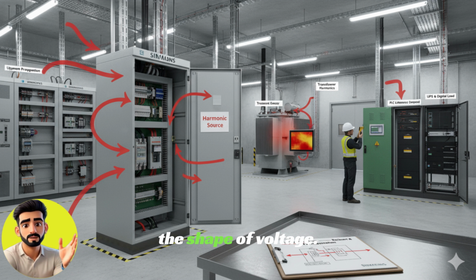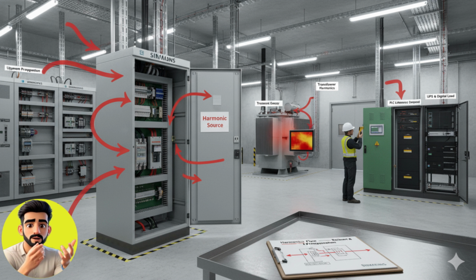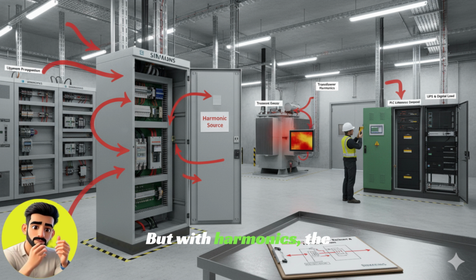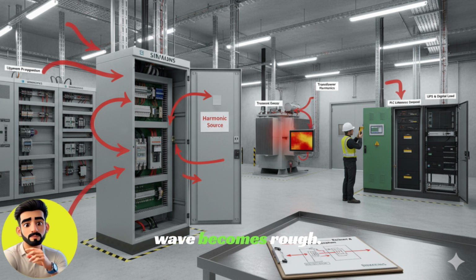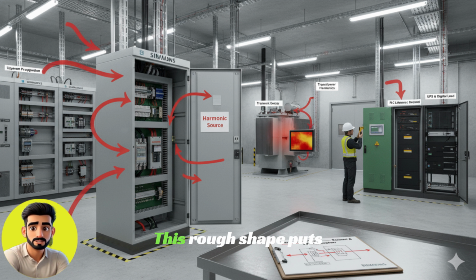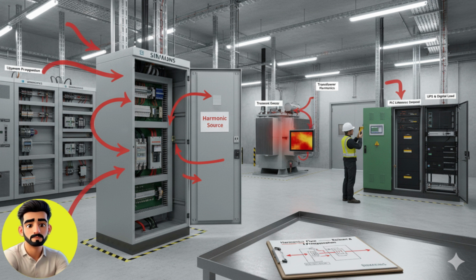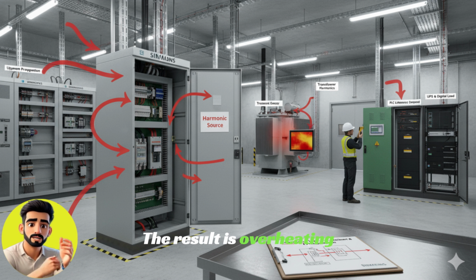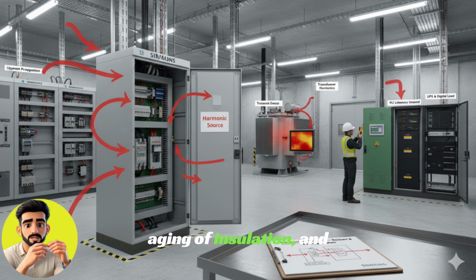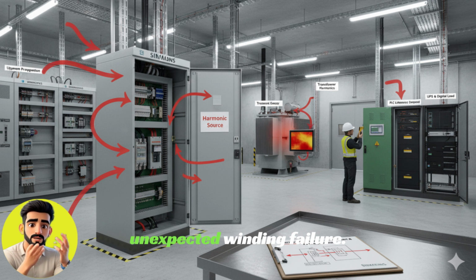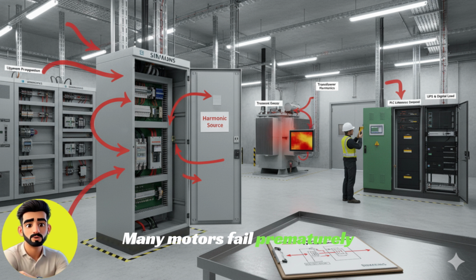Third point. Harmonics distort the shape of voltage. Under normal conditions, the voltage wave is smooth. But with harmonics, the shape of the voltage wave becomes rough. This rough shape puts extra stress on motor insulation. The result is overheating of motor windings, early aging of insulation, and unexpected winding failure. Many motors fail prematurely for this reason.